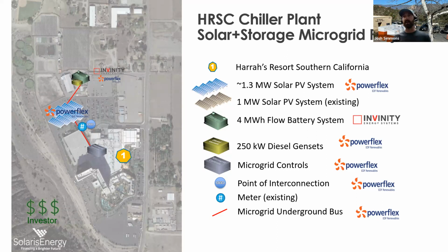You don't want your HVAC systems all ramping up at the same time, creating a giant spike that'll actually shut down your entire microgrid system and facility. So that's an important consideration, and an expensive consideration. Controls can be quite pricey as part of these projects. And then cybersecurity is also an important concern as well.